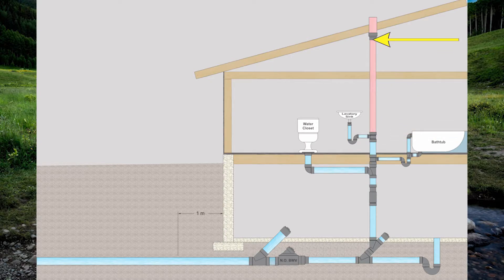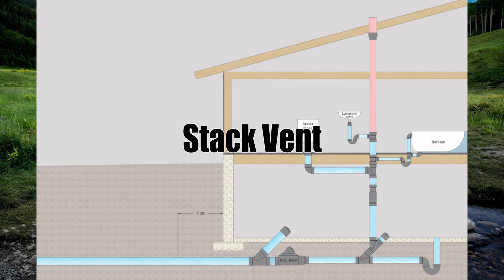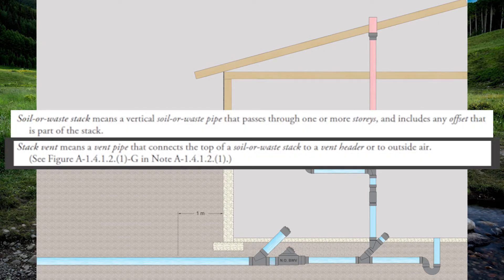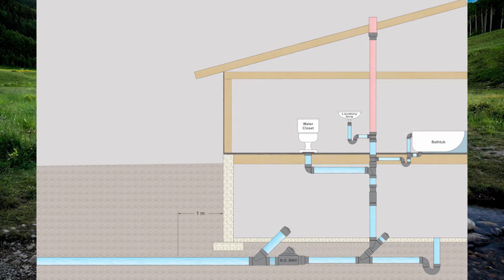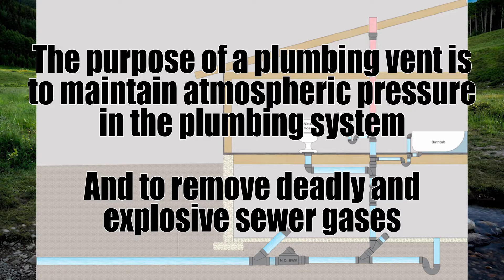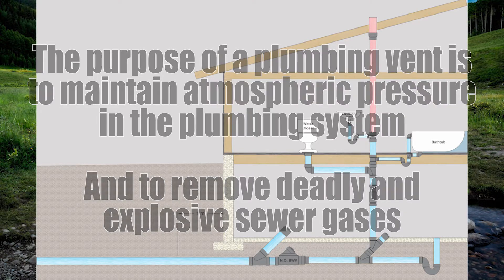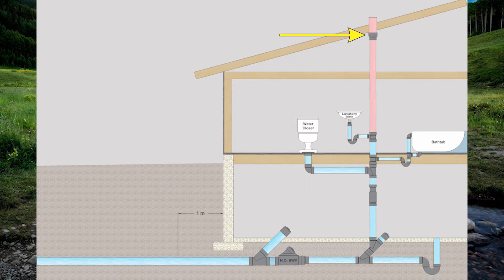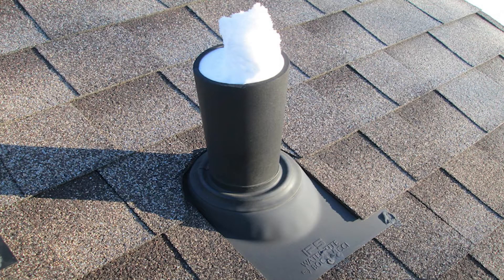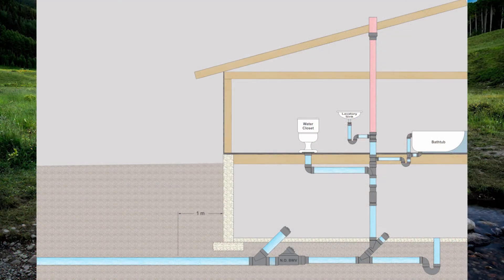The top of the soil or waste stack is right here, and then there's a red pipe that extends up through the roof. The top of every soil or waste stack must have a stack vent — that is what the red pipe is. Stack vent means a vent pipe that connects the top of a soil or waste stack to a vent header or to outside air. The purpose of a vent in a plumbing system is to maintain atmospheric pressure throughout the entire drainage system and to remove sewer gases, which can be poisonous or explosive. You'll notice the pipe size increases before passing through the roof — this is to prevent frost closure on cold winter days, which we'll cover in another video.